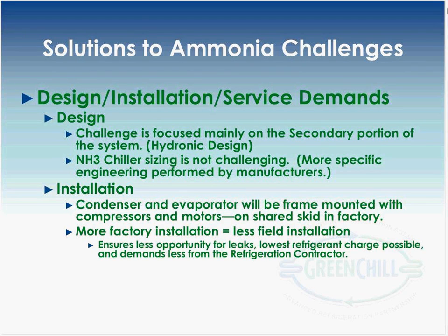assembled in the factory because we want the tightest factory-built ammonia system that we can get. As far as the ammonia side, it's going to be a matter of probably just sizing the compressors and the heat exchangers, which would put no real new design demand. I think for a lot of refrigeration engineers, it's been more the hydronic side that's required more heat on the design for that.